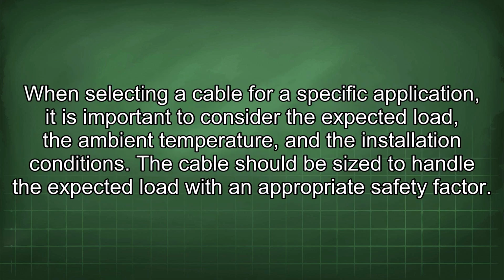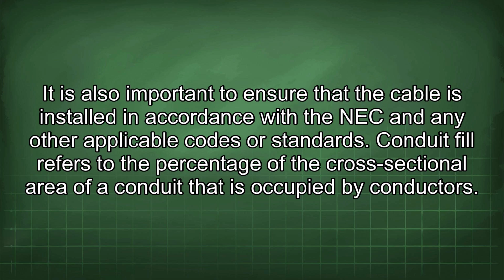When selecting a cable for a specific application, it is important to consider the expected load, the ambient temperature, and the installation conditions. The cable should be sized to handle the expected load with an appropriate safety factor. It is also important to ensure that the cable is installed in accordance with the NEC and any other applicable codes or standards.